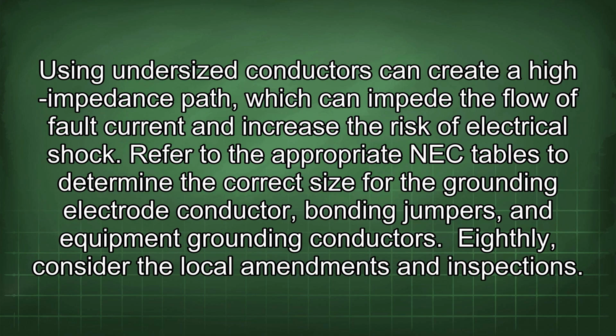Using undersized conductors can create a high impedance path which can impede the flow of fault current and increase the risk of electrical shock. Refer to the appropriate NEC tables to determine the correct size for the grounding electrode conductor, bonding jumpers, and equipment grounding conductors.